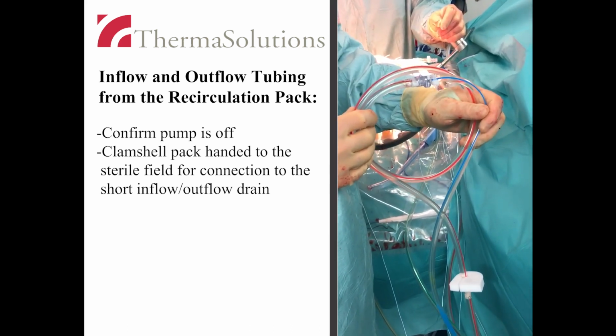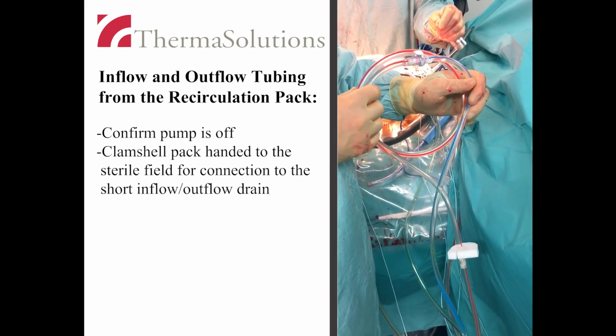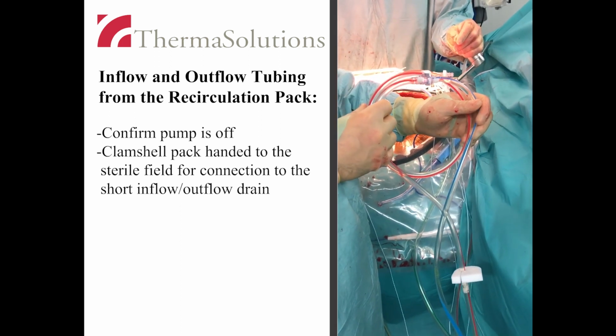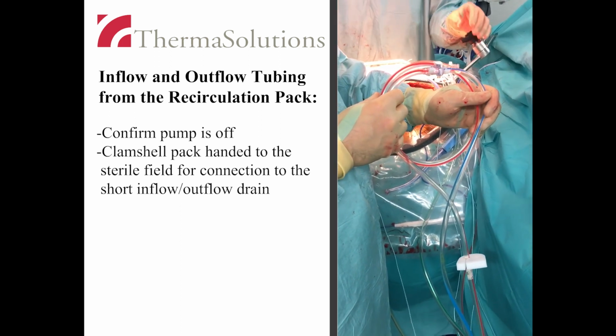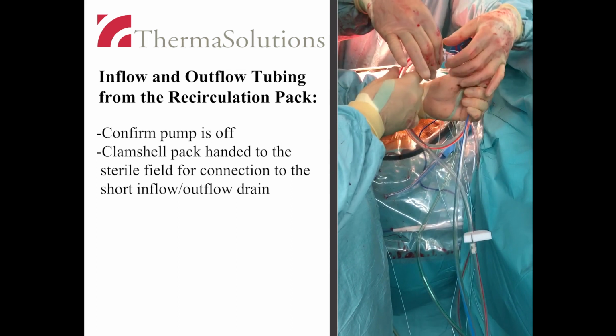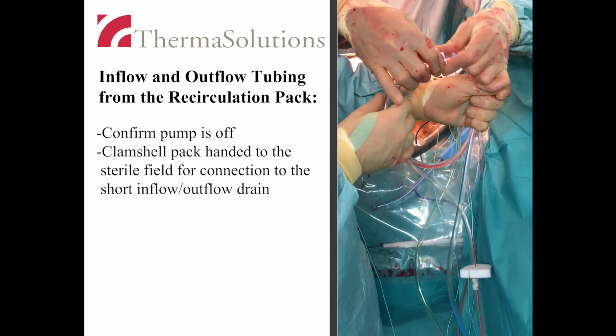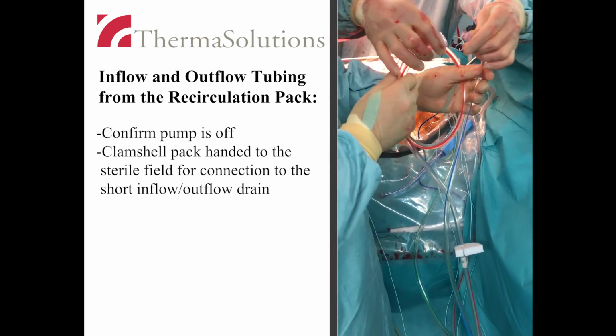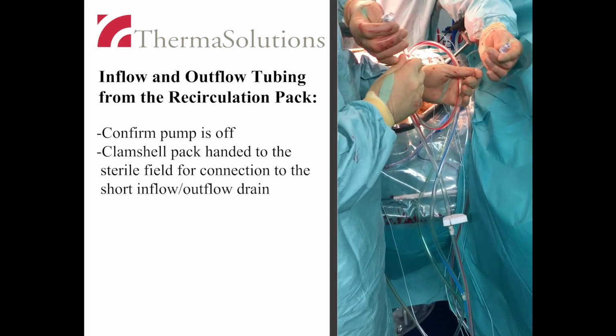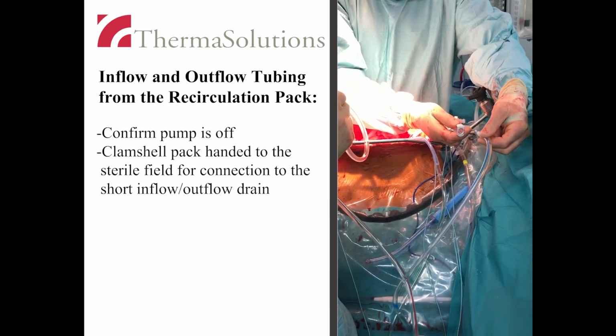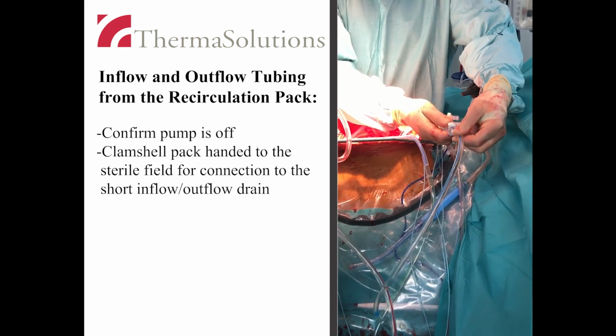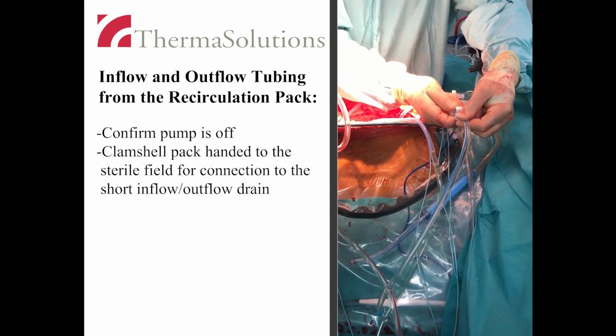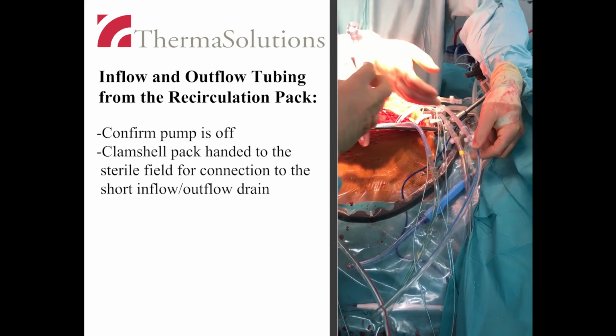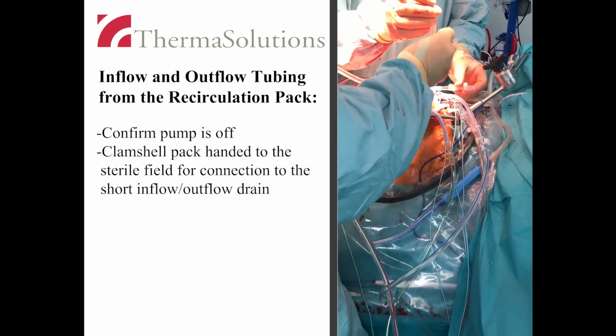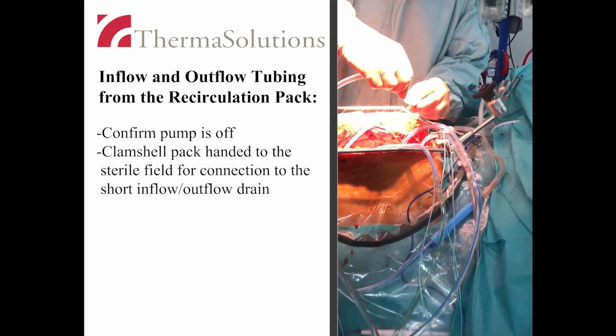The sterile, non-sterile demarcation on the tubing is pre-marked with tape. Once on the surgical field, the coil is separated using the quick release fitting. The short inflow cannula is connected to the inflow line, which is identified with a red stripe. The short outflow cannula is connected to the outflow tubing, which is identified with a blue stripe.